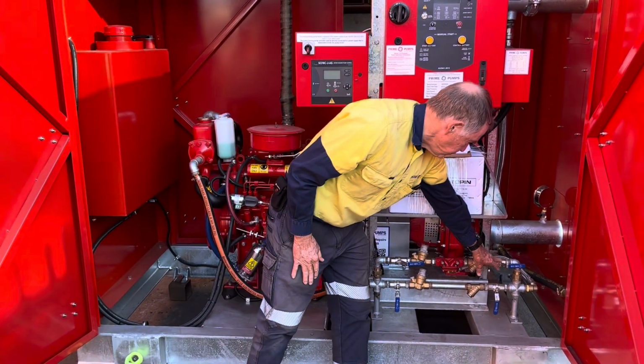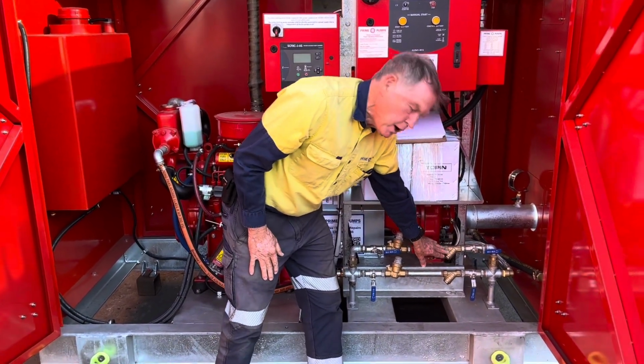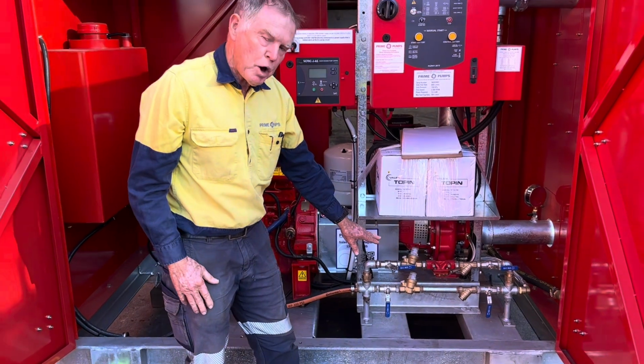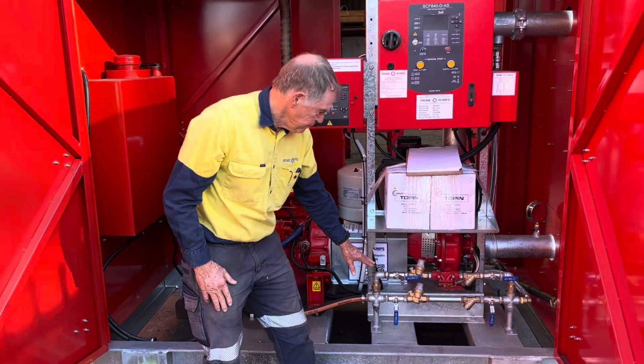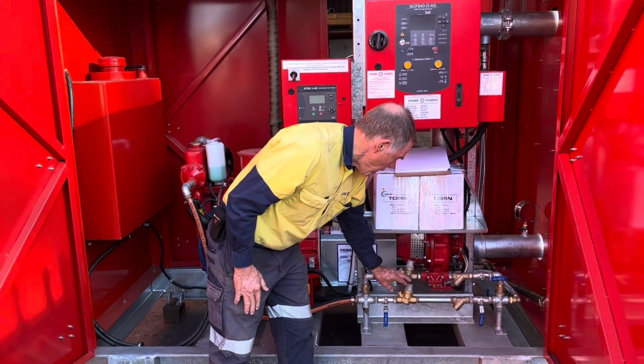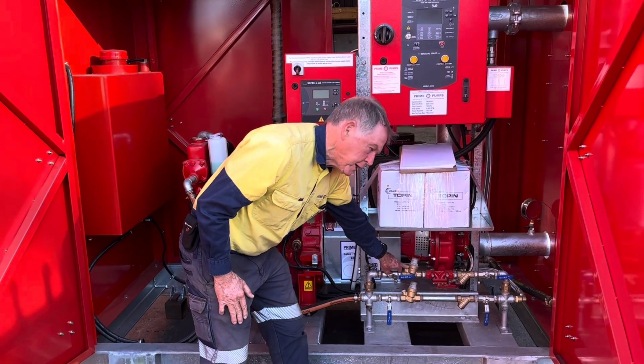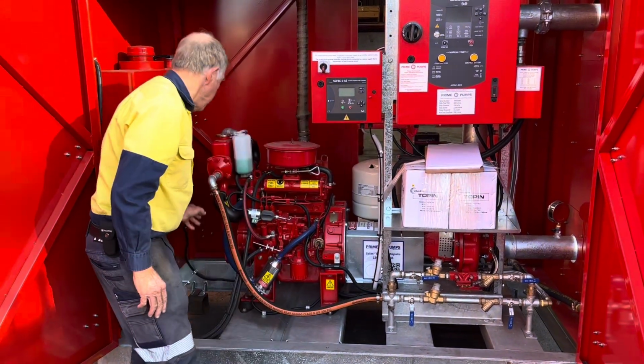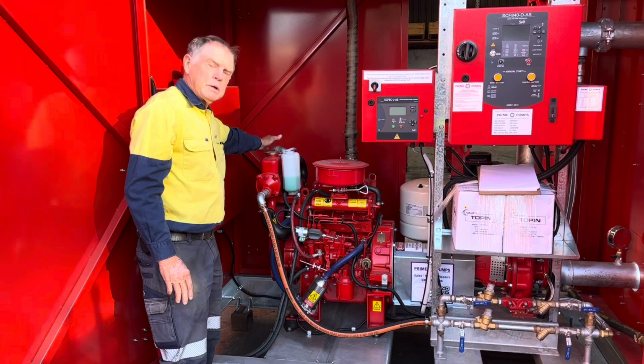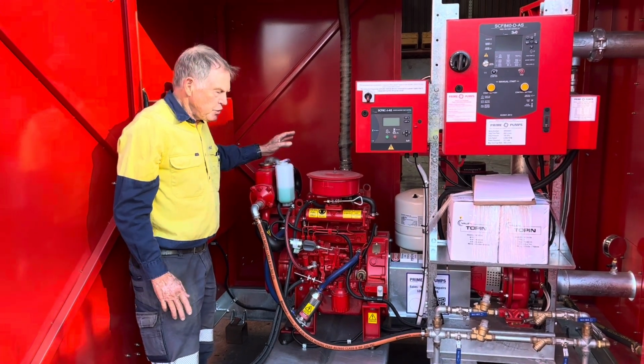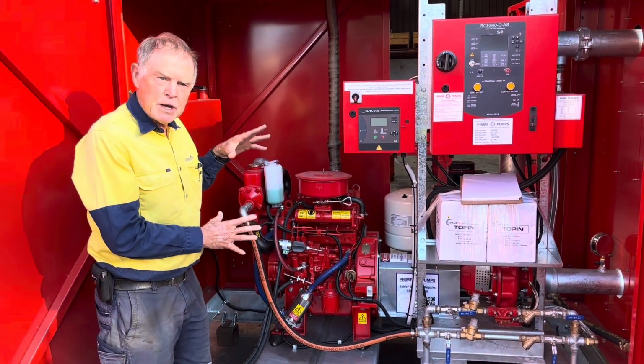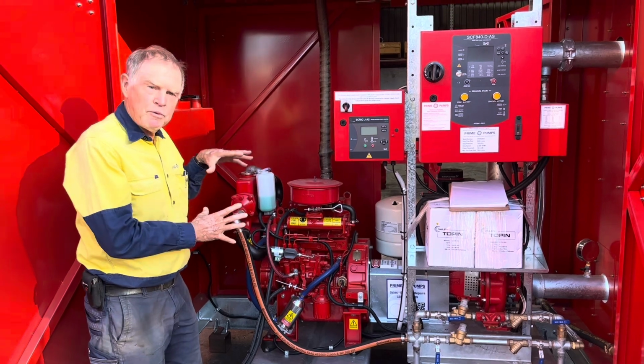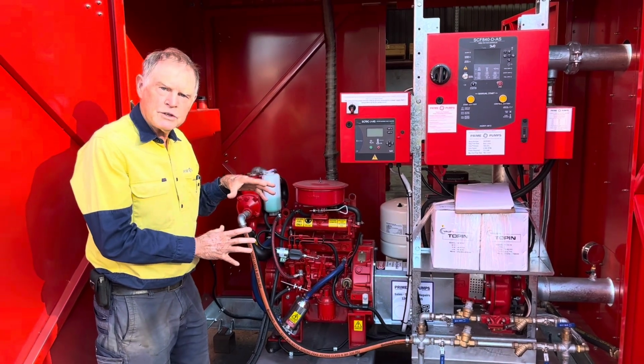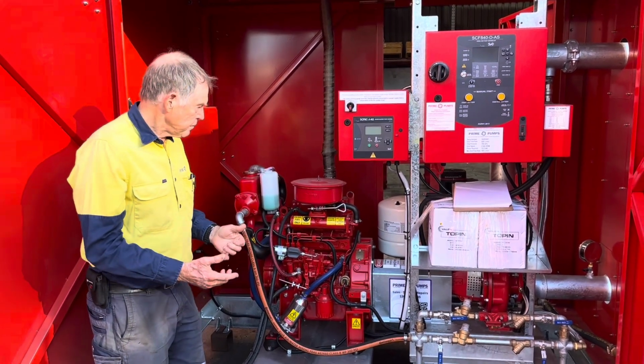The water comes through this valve, through the Y strainer - we'll talk about those more later on when we're doing our 6 monthly checks - through the control valve, through this pressure regulating valve, up to the heat exchanger, and then ultimately is plumbed to waste. So the heat that's being produced during the combustion process in this type of engine goes out through the floor waste and into the drainage system.